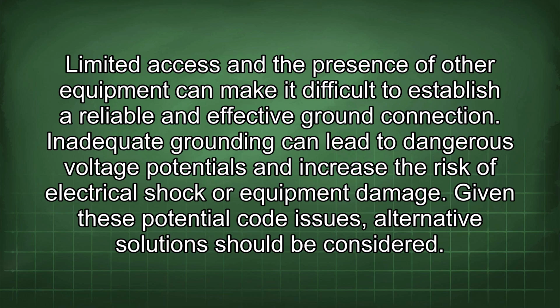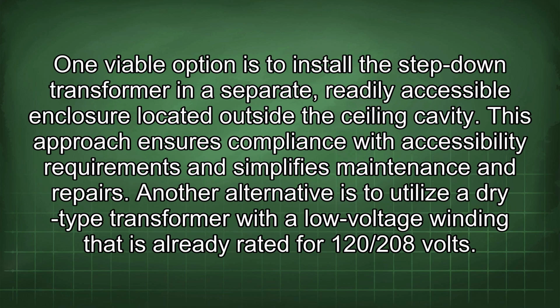Given these potential code issues, alternative solutions should be considered. One viable option is to install the step-down transformer in a separate, readily accessible enclosure located outside the ceiling cavity. This approach ensures compliance with accessibility requirements and simplifies maintenance and repairs. Another alternative is to utilize a dry-type transformer with a low voltage winding that is already rated for 120/208 volts.